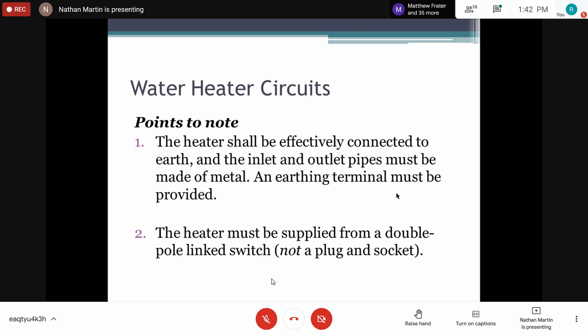All right, points to note: the heater shall be effectively connected to earth, meaning that the casing of the heater must be earthed. The inlet and outlet pipes must be made of metal, so you cannot use PVC, right? That is why when you look at an electric water heater, where you make the connections, they would have used a galvanized fitting. An earthing terminal must be provided, meaning that the water heater will have an earthing terminal where the connections are made. The heater must be supplied from a double pole link switch, not a plug-in or socket.